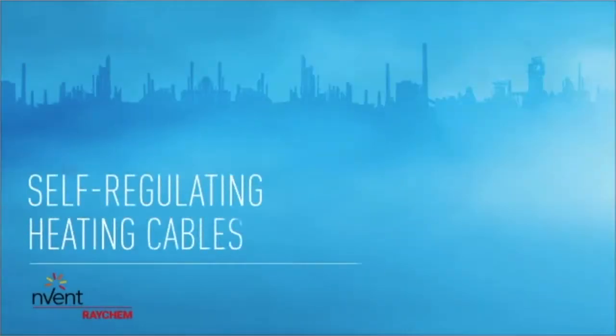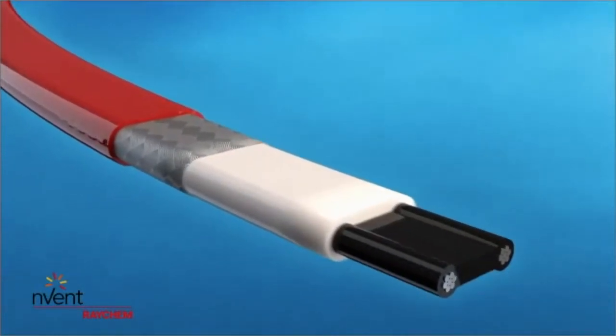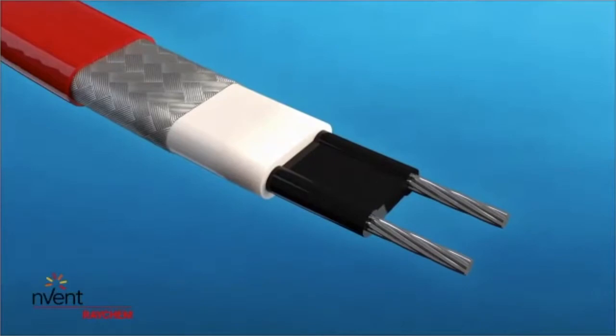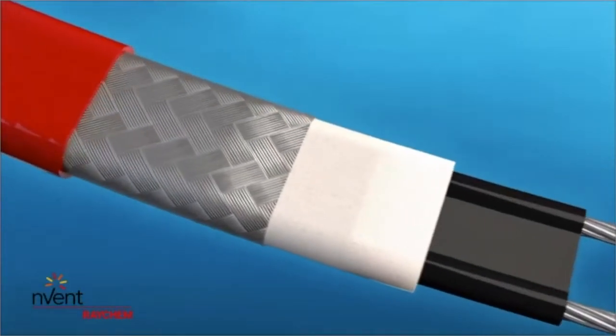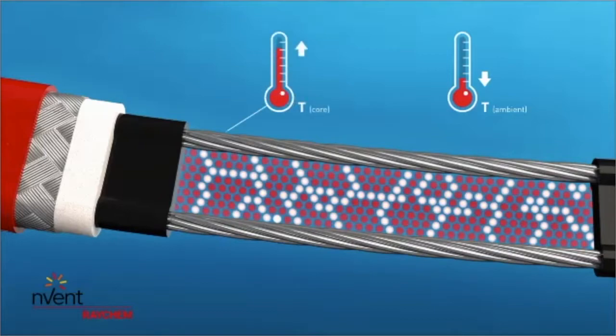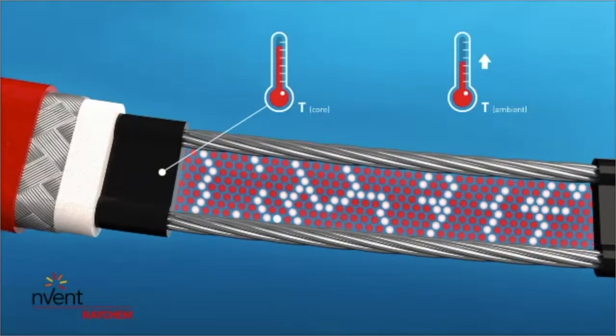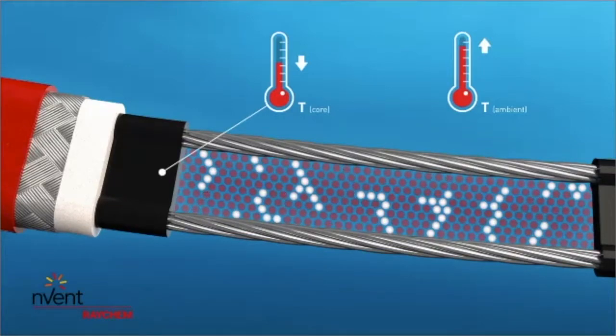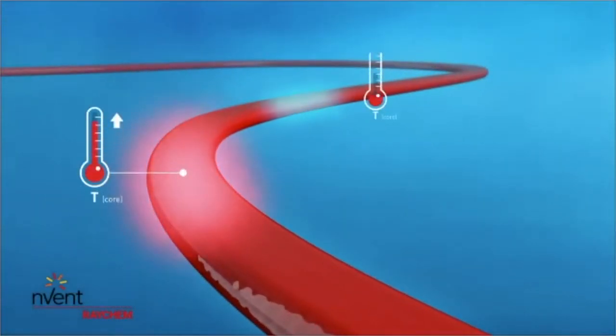Raychem self-regulating heating cables automatically adjust their power output to compensate for temperature changes. The outer jacket, braid, and inner jacket provide mechanical, chemical, and electrical protection. But the magic happens in the conductive core that surrounds the two parallel conductors. As the ambient temperature drops, the core contracts microscopically and the number of electrical paths through the core increases — more heat is produced. Conversely, as the ambient temperature rises, the core expands and has fewer electrical paths — less heat is produced. At a certain temperature, almost all electrical paths are disrupted and power output is close to zero. A self-regulating heating cable adjusts its power output along its entire length, making it a safe and reliable solution for many applications.